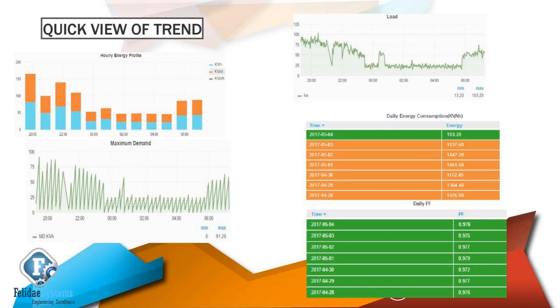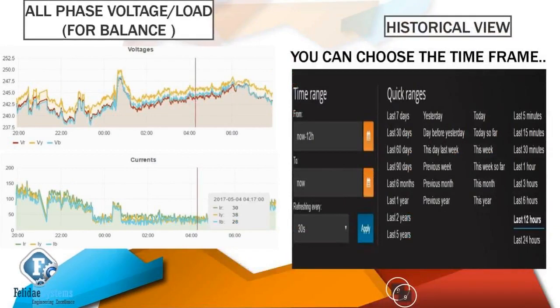This is useful in both cases: if your plant faces a maximum demand penalty, or if it has an excessive sanctioned load and can save by reducing the contract demand, both are very useful. Sometimes, whether the plant is running or not, we have to pay fixed charges. If we can reduce it, or need to increase it, and if we see the maximum demand crossing a limit, we can optimize the process by examining why it happened. We can see this by looking at the history of the maximum demand data, which we'll go through in the live demo.